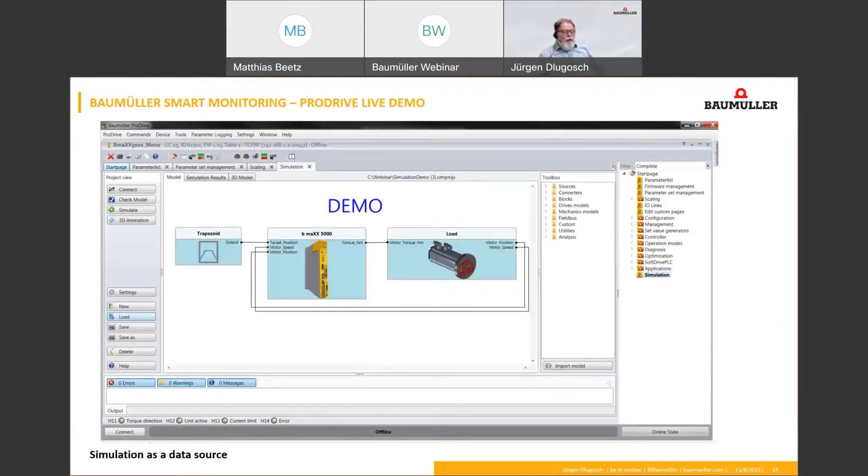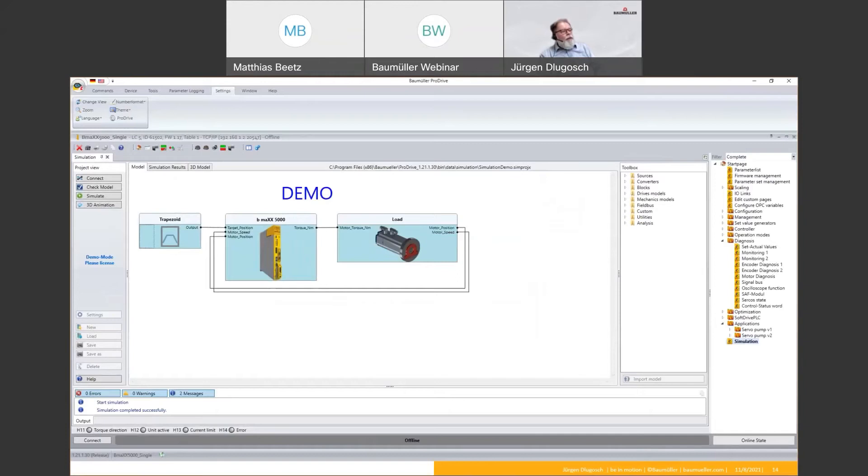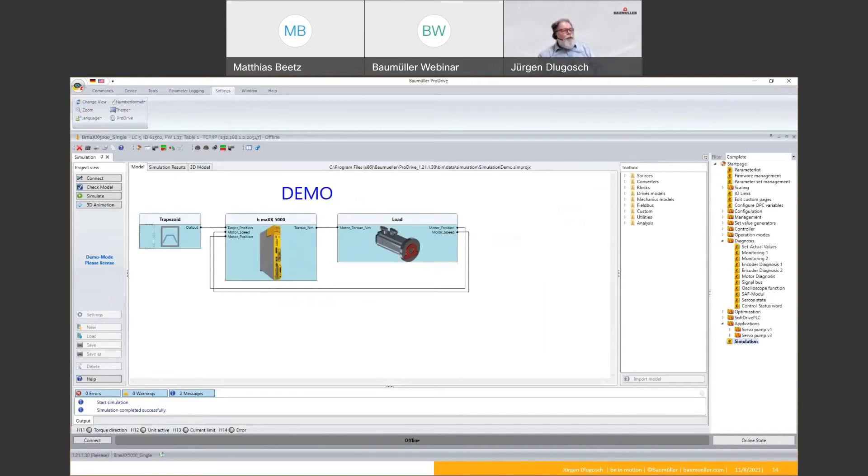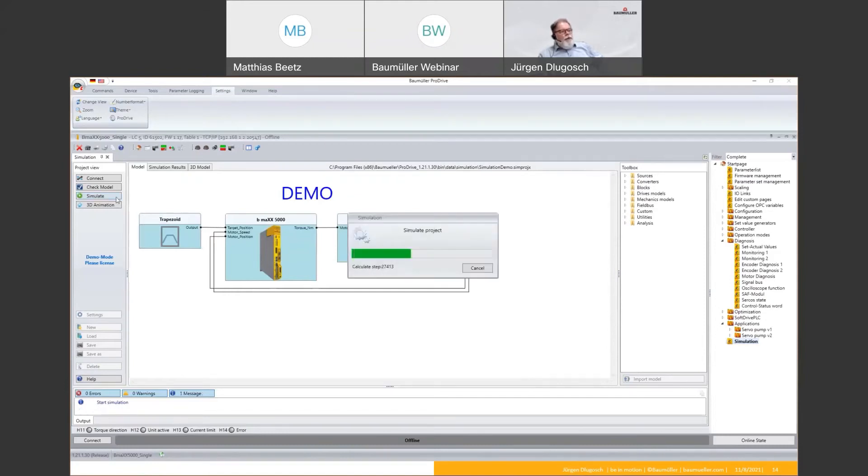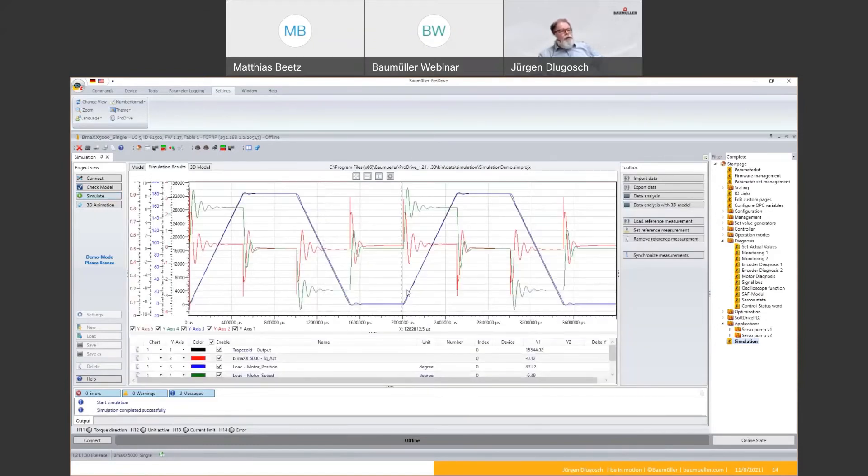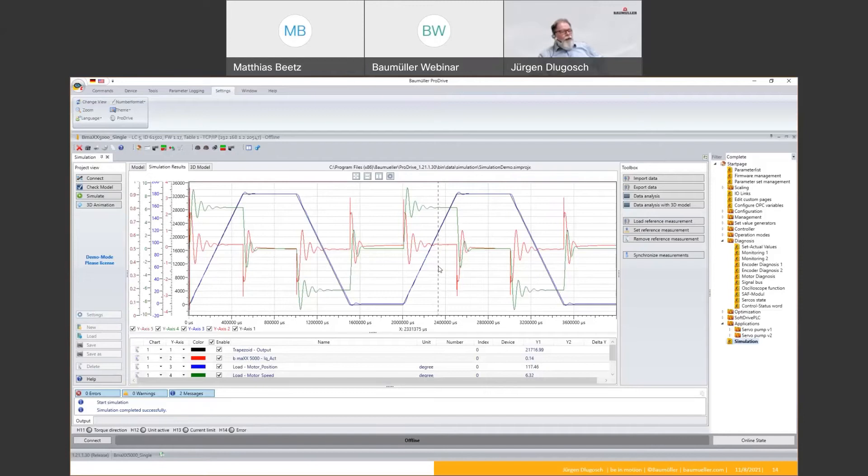Next, I want to show you the functionality of the Smart Monitoring function on ProDrive. This is a live demo. For this, I'm using a function which is also in a demo mode inside the ProDrive. This is called ProSimulation and with ProSimulation I can make a model of my application. Here you can see it, for example, it's a model done by a load, a motor, and also a model of the drive. And you have a set value generator for giving some speed or some position commands and so on. Of course, we can simulate this. Then we get a result which is near the reality because we use very good models of our motors and also from the drive side. So the differences to the reality is very small.